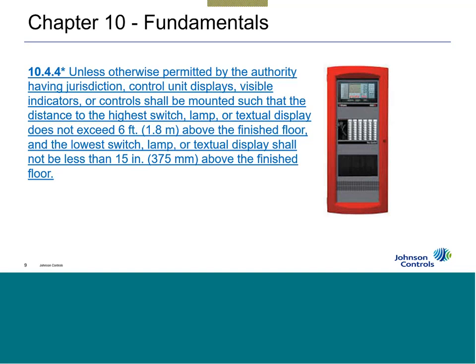Now, something that's new for 2019 is how high and how low the fire alarm control unit can be on the wall. And as a person who's been in the industry for a very long time, it makes you scratch your head and think, why didn't they do this a long time ago? And that's kind of what the committee said when they were around the table talking about this. It's like, gee, what do you mean there's nothing in there about how high or how low? Yes, you could kind of sort of get there in the NEC, the National Electrical Code, for electrical cabinets and how they should be mounted on the wall, but it didn't specifically say fire alarms shall be mounted to this height.